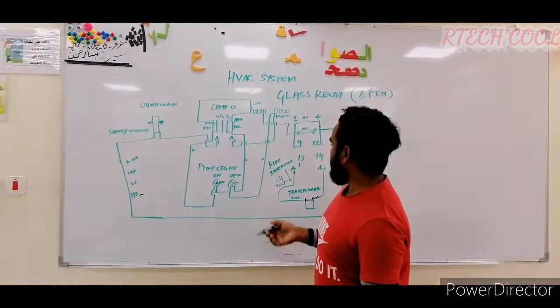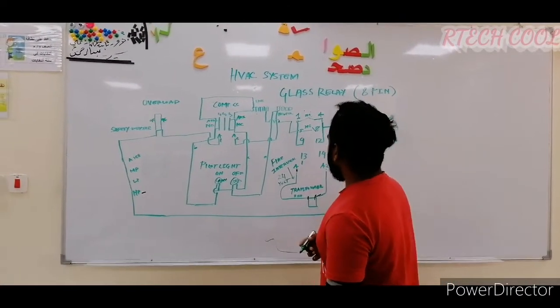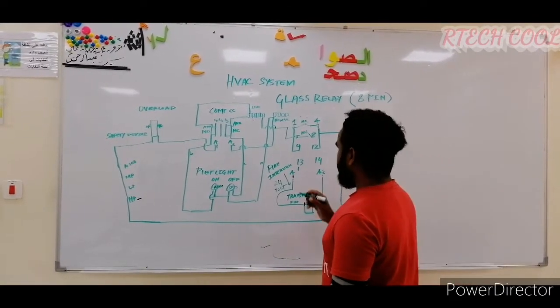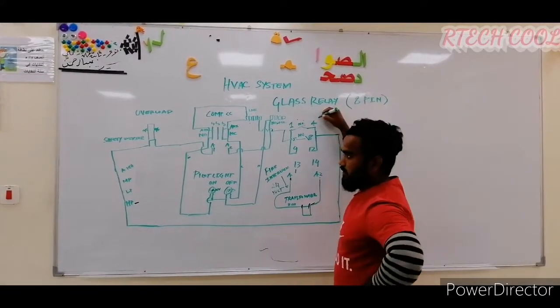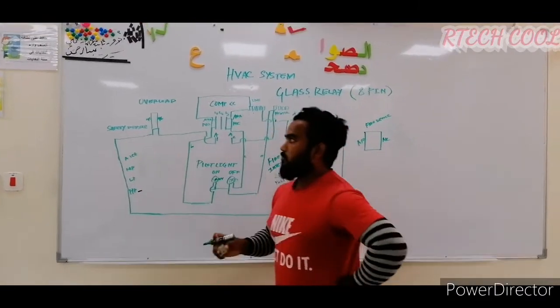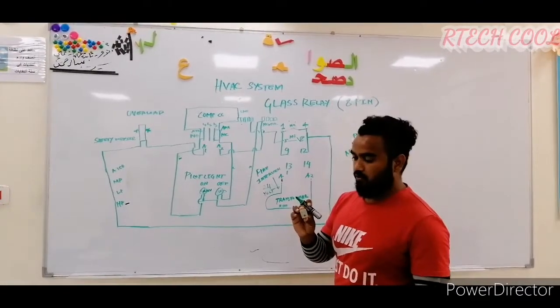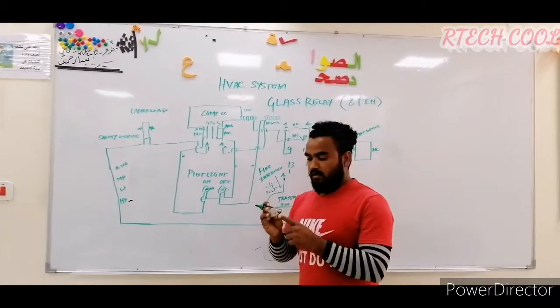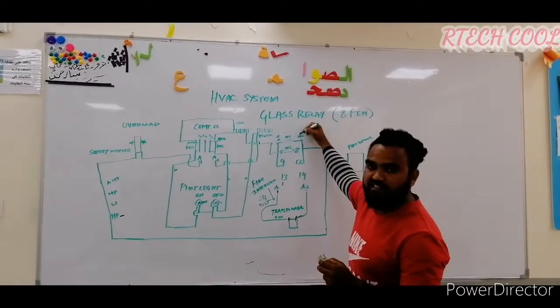In our actual system, we are using it as a fire alarm interlock. In this glass relay, there are 9 points. If you have this relay, or wherever you go in our HVAC system, you can see there is a 9-point relay. Points 1 and 4 are NC points — always NC.